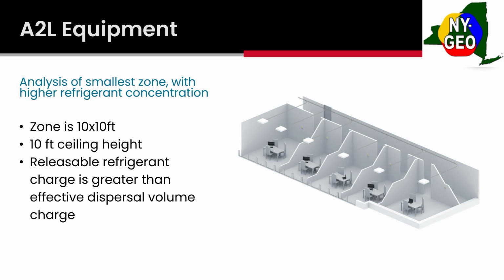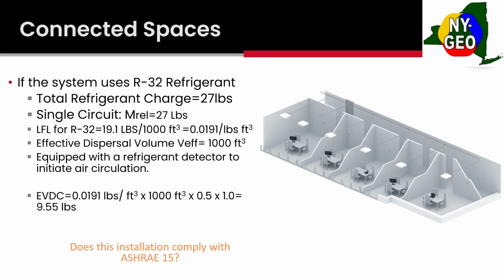All right, so we'll get into the design considerations real quick. So here's a typical VRF system in our office. We've got indoor heads in each office here. Each office is 10 by 10, with 10-foot ceilings. Again, the releasable charge cannot be greater than your effective dispersal volume charge, your EDVC. This is how we typically design something. And these could be water source heat pumps too. So if we're using R32, our total refrigerant charge is 27 pounds. Our releasable charge on a single circuit is 27 pounds.